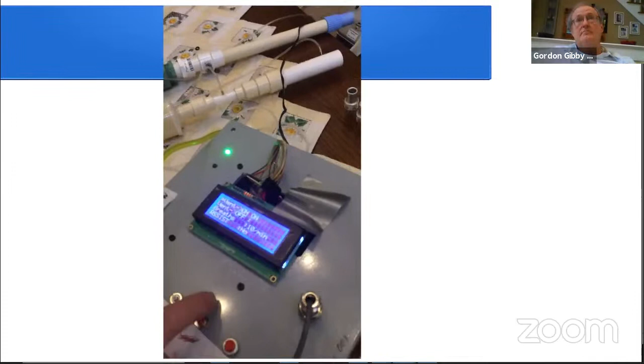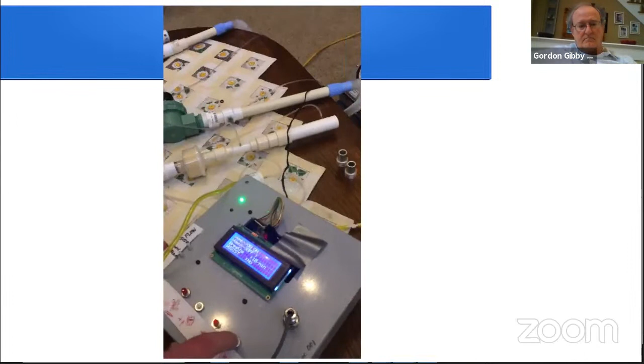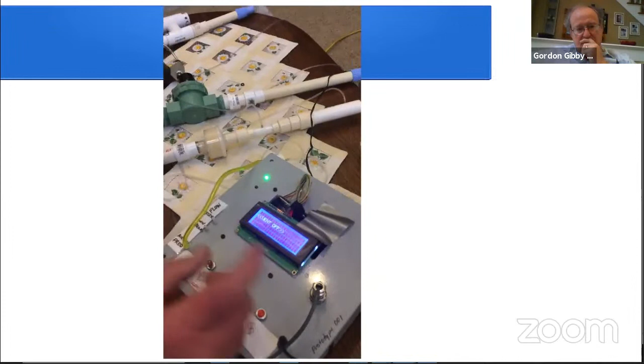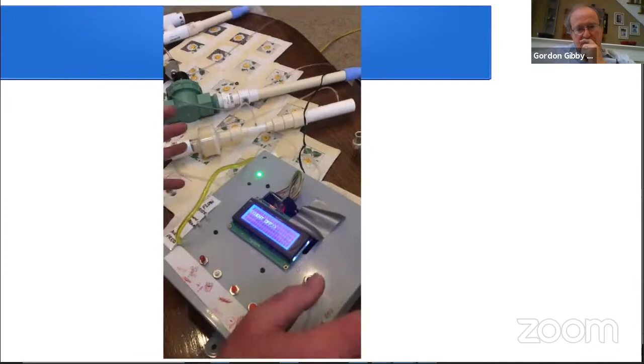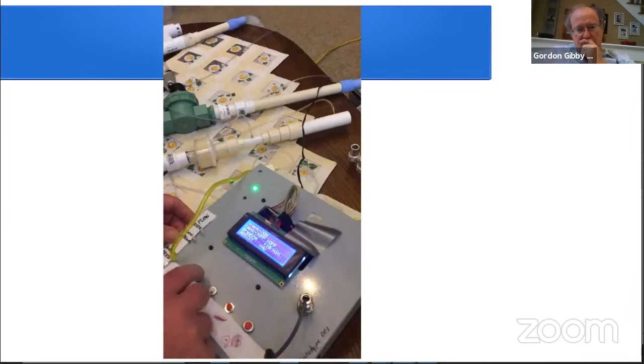While I'm using this, I'll probably set some alarms off because I'm going to change a lot of things. If I want to turn the ventilator off, I have to go through quite a few steps. I have to go off, and then I have to confirm, and then I have to do it again, and now the ventilator is finally off. There is no means to turn this off. It's got no power switch. Once it's powered, and normally there's a battery built in, it's impossible to turn it off. It's intended to be used and monitored by biomedical engineering.